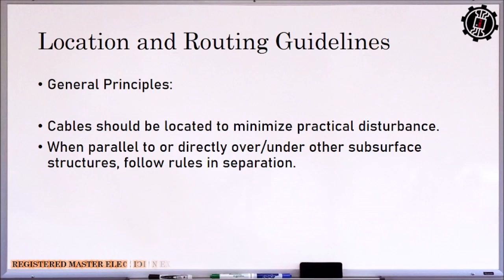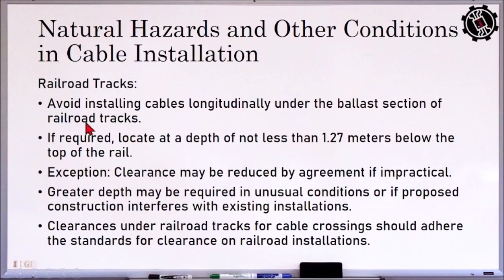In buildings and other structure, avoid direct installation of cable under building foundations. So sa mga foundation nating building, bawal yon. If necessary, support the foundation to limit the likelihood of transferring detrimental load on the cable. Then railroad tracks. So katulad pa yan. So mga dadaanan ng train. So avoid installing cables longitudinally under the ballast section of the railroad tracks. So yung nasa mismong ilalim ng railroad. If required, locate at a depth not less than 1.27 meters below the top of the rail. And exception clearance will be reduced by agreement if impractical.